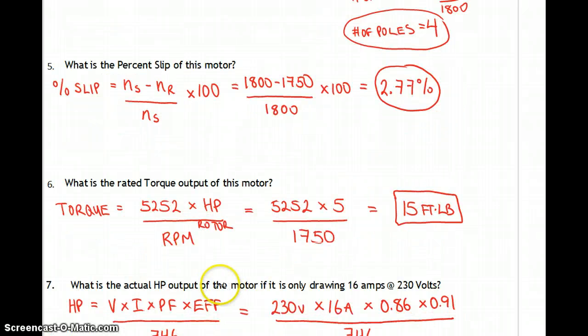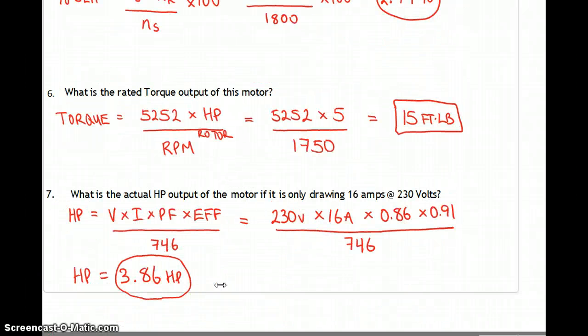Rated torque: torque equals 5,252 times horsepower over rotor RPM. So 5,252 times 5 horsepower over 1,750 — this small 5 horsepower motor gives us 15 foot-pounds of torque. Next, what's the actual horsepower output if the motor is only drawing 16 amps?